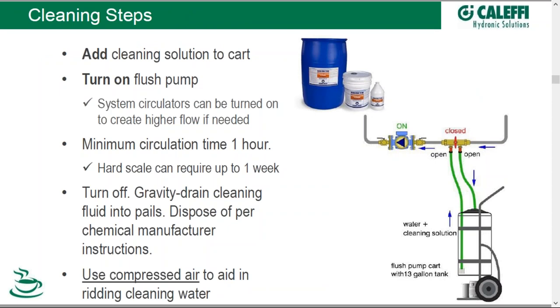Your steps in cleaning would look something like this. We have our cleaning chemicals — this is Romar's version — and we want some means of pumping our cleaning solution into and back out of our system. Pumping carts such as this one from Caleffi do the job. We start by putting our cleaning solution at the required concentration in the pumping cart, turn on the pump, and send fluid through the system. When it comes to cleaning, oftentimes faster flow is better than slower flow, and you can turn on your system circulators to help speed the process along.